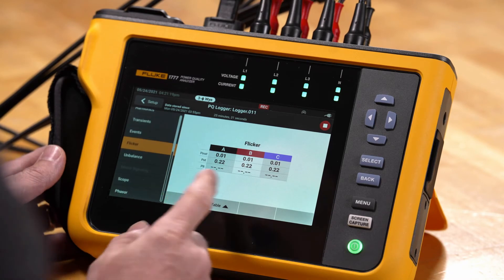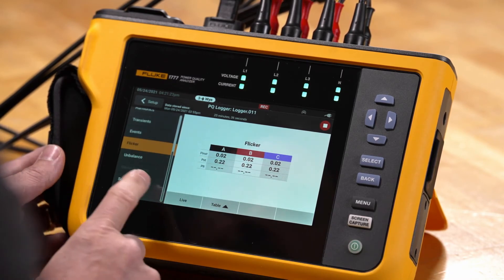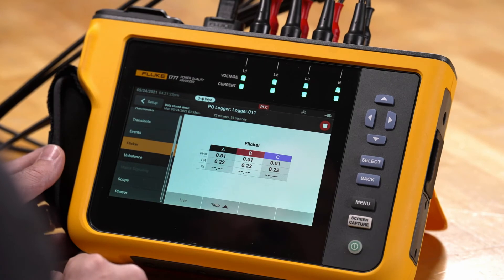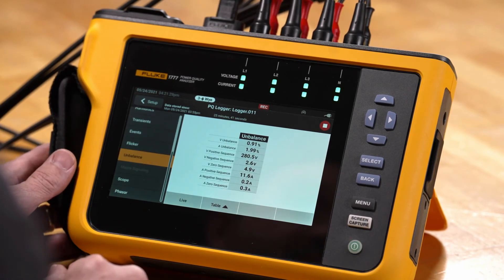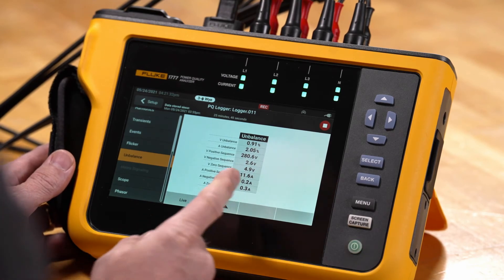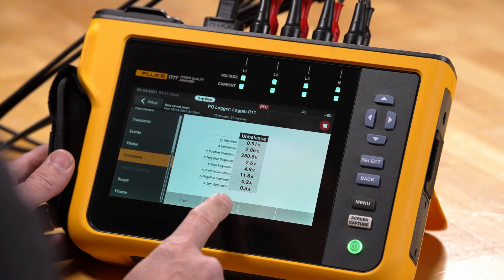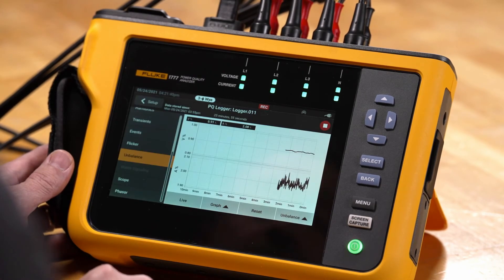We don't have any long-term flicker because the recording hasn't been going on long enough. We can look at unbalance data — for example, if you're doing motor testing, we can see what kind of unbalance we're looking at for voltage and current unbalance and see those numbers live. We can also go to a graph view to see that information.